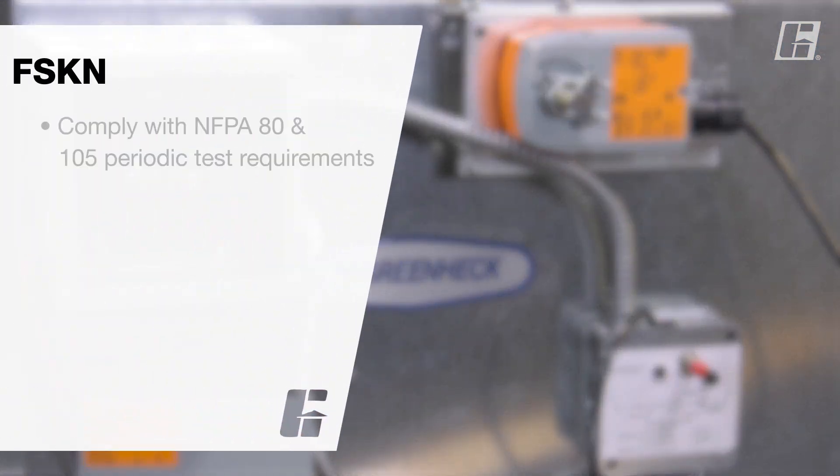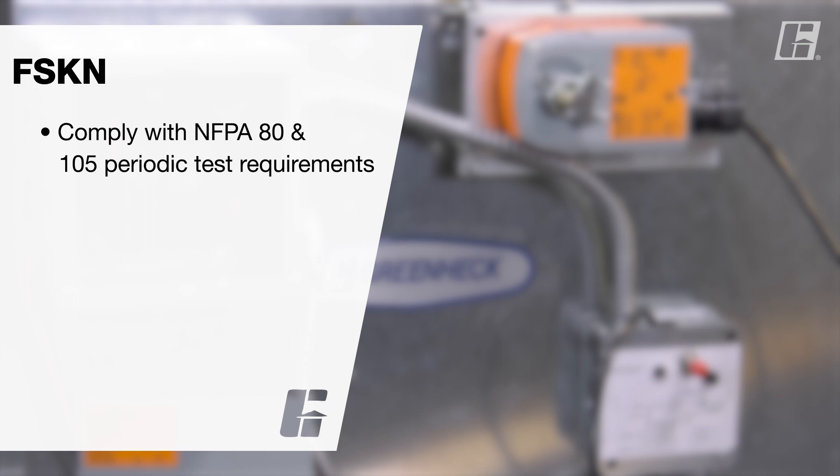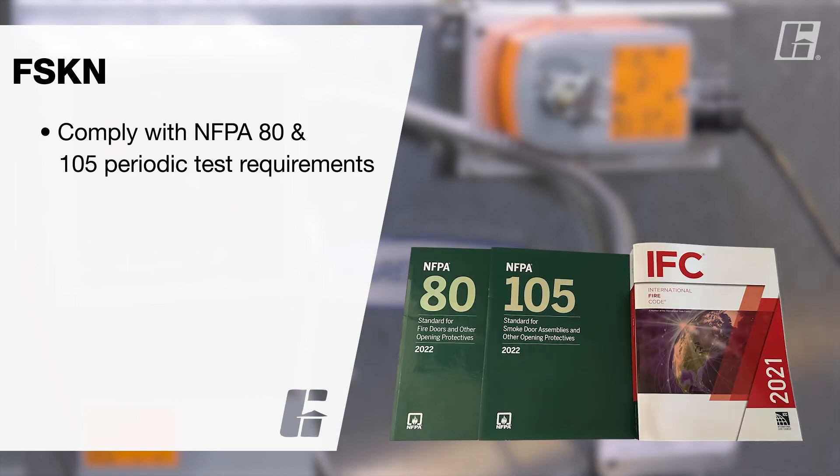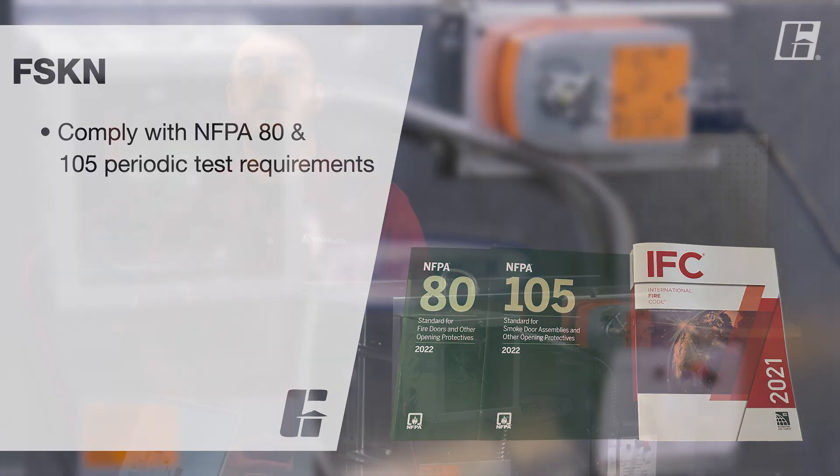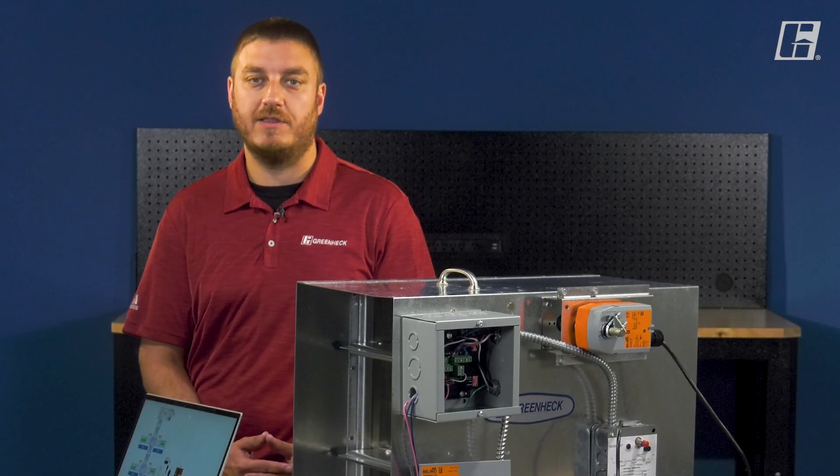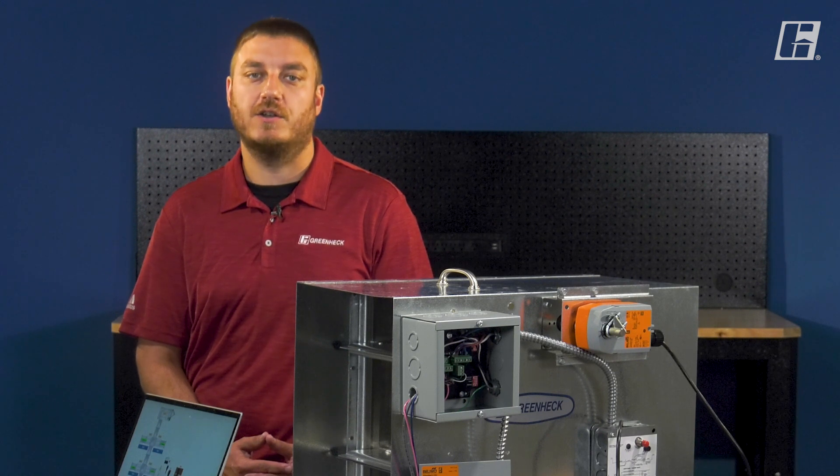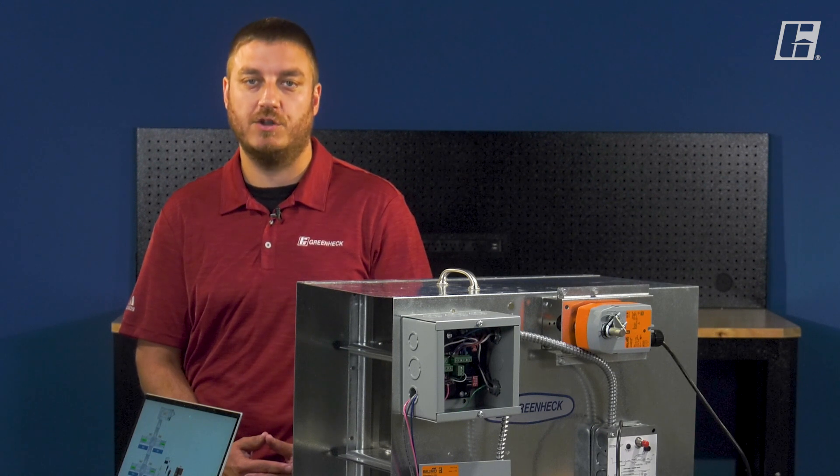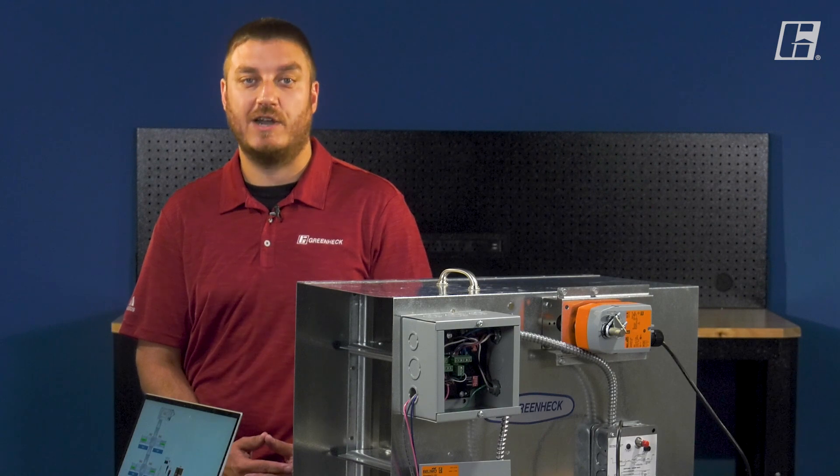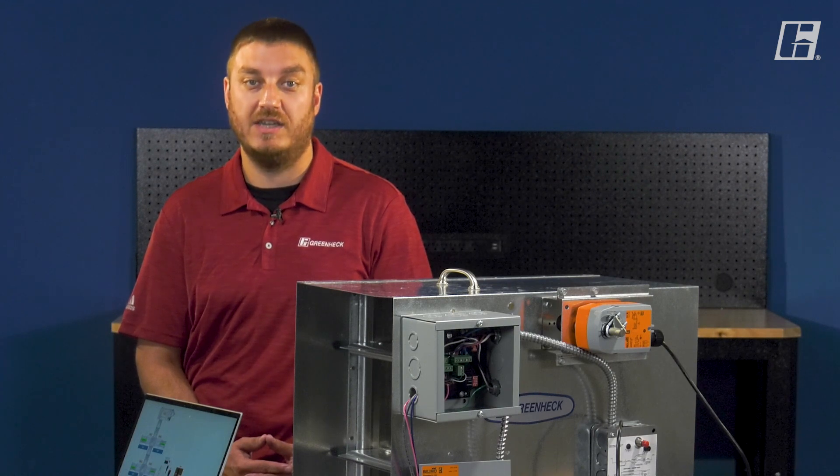The International Fire Code, as well as local fire codes, require that fire smoke dampers be maintained in accordance with NFPA standards 80 and 105. These NFPA standards require that smoke and fire smoke dampers be periodically tested to confirm that they will operate properly during a fire event and test records be maintained for the prior three test cycles.